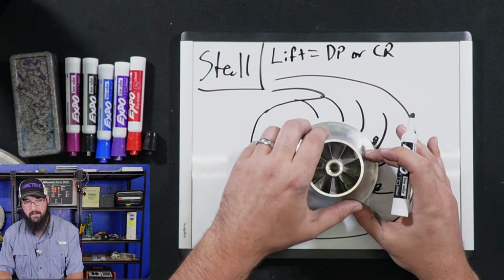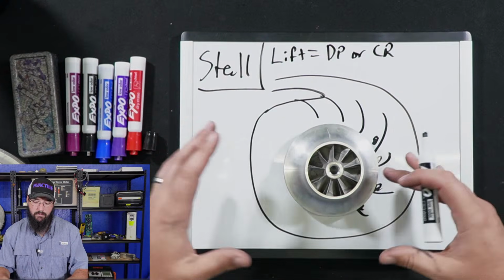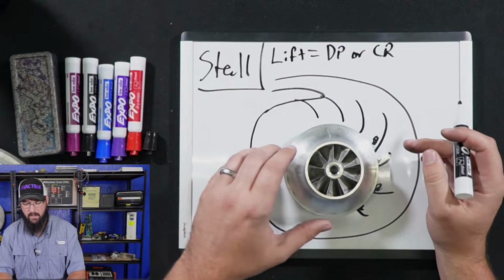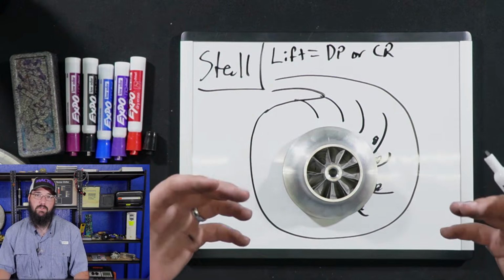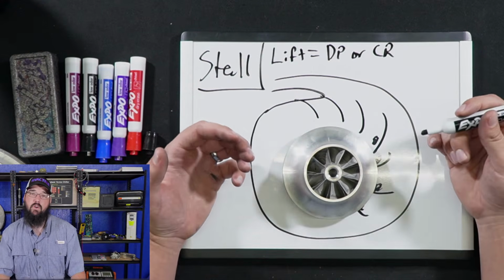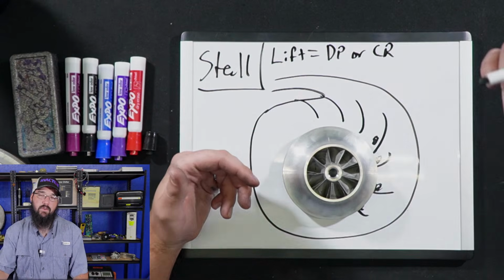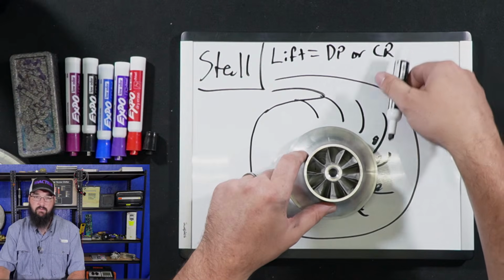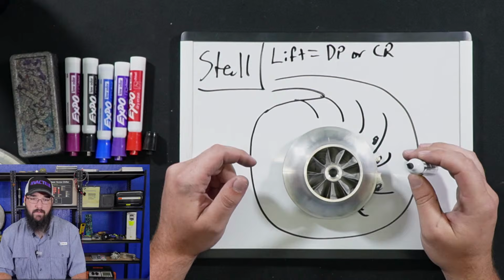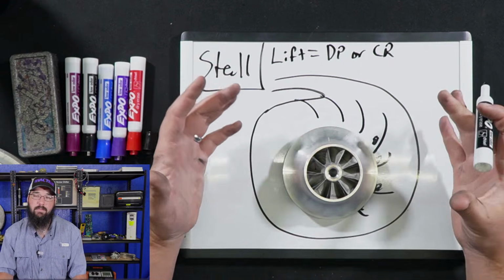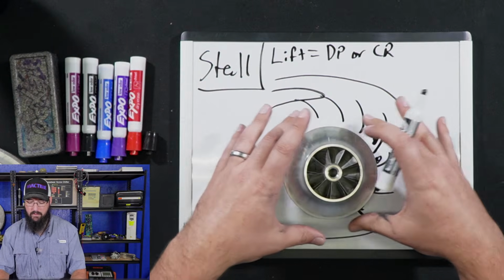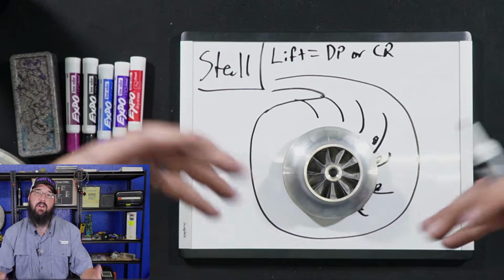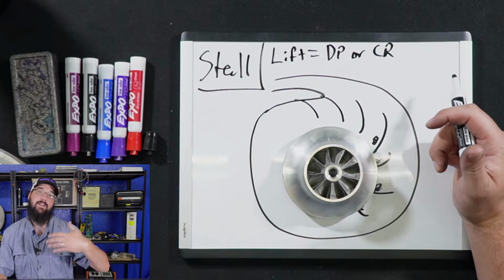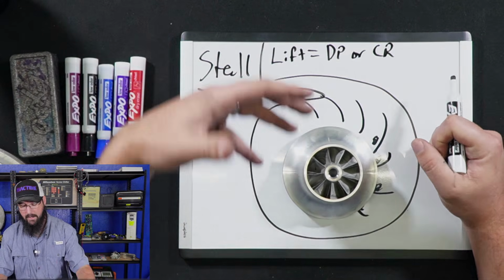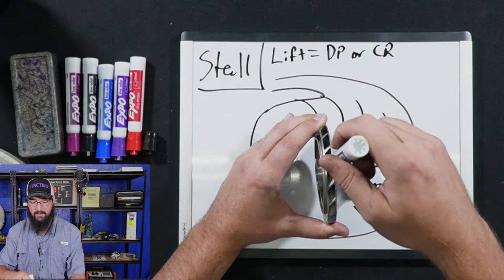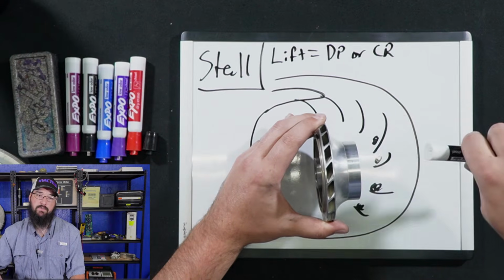It is, hey, this section right here, as this impeller rotates, because we have a high lift and we're struggling to maintain flow through the impeller because of lift, leads to a stall condition, what we would call stall. Now, the extreme of a stall, once we move past just stalling, we can trip over what's referred to as surge, and surge is where the refrigerant reverses flow back through the impeller. That's when we exceed the impeller's ability to hold the lift at all and get into an unstable state. Then we completely overcome its ability to add enough energy to the refrigerant to overcome the condenser pressure, basically. You can think of it like that. And then the refrigerant literally comes in the outlet side and back out the suction and reverses flow.